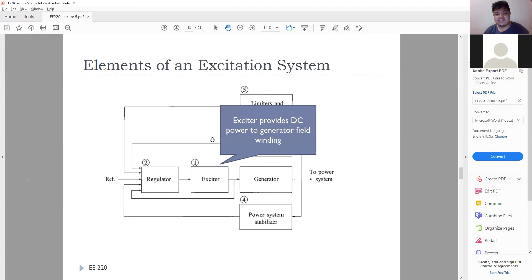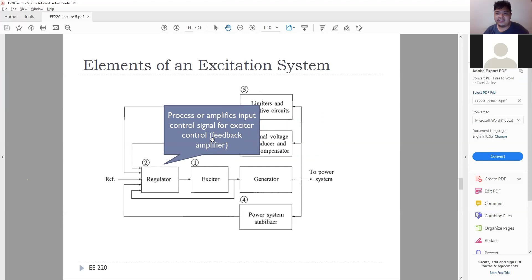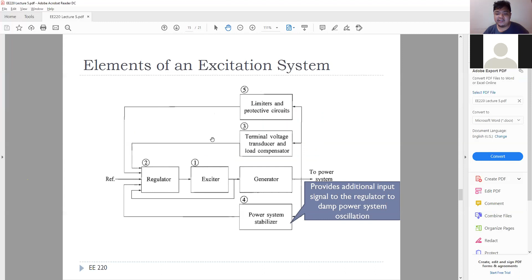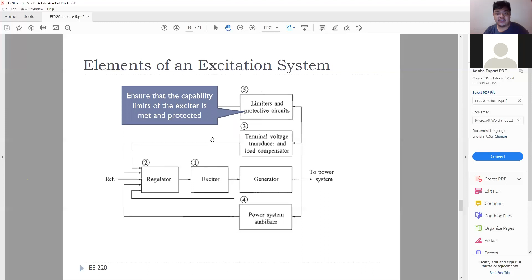Okay, yan. Exciter provides DC power to generator field winding. The regulator processes or amplifies input control signals for exciter control or feedback amplifier. Whereas the power system stabilizer provides additional input signal to the regulator to damp power system oscillation. Limiters and protective circuits ensure that the capability limits of the exciter are met and protected. So yan yung parts ng ating excitation system.